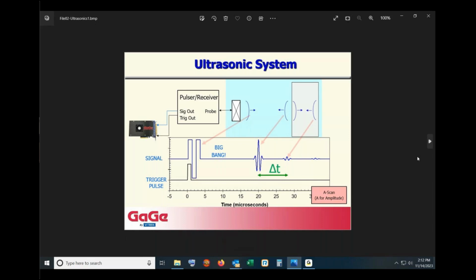As an overview, here's a generic ultrasonic system. The heart of it is this box with the X, the ultrasonic transducer, which when excited with a very short, high-voltage pulse, usually up to around 300 volts, emits a ping of ultrasound. We can see this pulse in water. In this case, we're using water as a buffer medium between the transducer and the slab of metal that serves as a sample. When the transducer is excited, the pulse travels towards the sample. At the same time, out the back of the pulser/receiver, we have an output signal. I should say that we're operating this transducer in reflection mode. So it's responsible for both emitting the ultrasonic ping and receiving echoes coming back, much as you would yell hello at a mountain and listen for the echoes coming back.